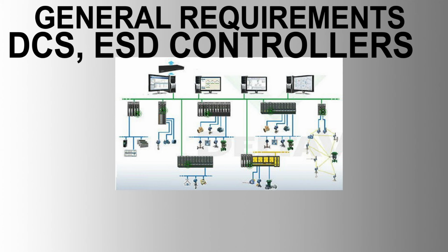Fault monitoring and testing. The ESD system shall include self-test and fault detection systems. As a minimum, the fault detection system shall monitor and annunciate faults in power supply, input-output circuits, interfaces, logic controllers, and output voting relays. Any failure in the monitoring circuit shall be alarmed, and it shall be possible to monitor and test the components comprising the ESD panel while the system is in normal operation.